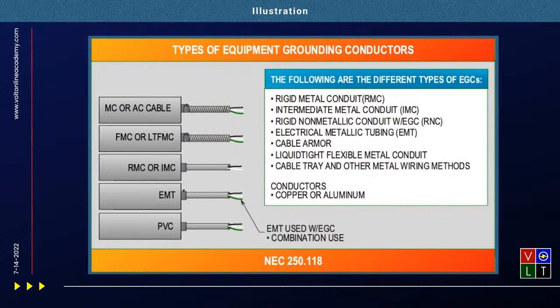It should be good. Well, what I did, I put a little diagram together, well, we actually had a diagram, I just got everything in color and all that. And when you look at 250.118, and you look at your types of equipment grounding conductors, you'll see in there that it lists EMT and then talks about the others. You'll notice we talk about the EMT, and I've got it highlighted there with an arrow. This is just exactly how it looks in the design book, and we talk about it being a combination use here with the equipment grounding conductor.